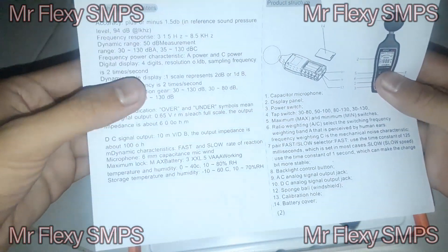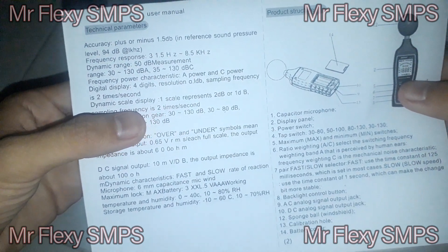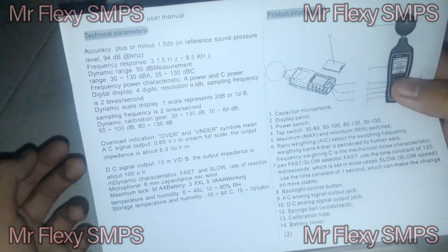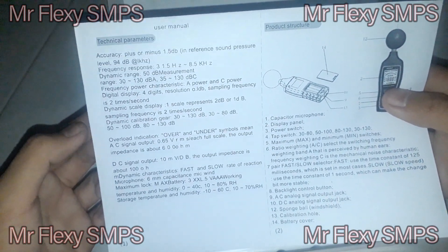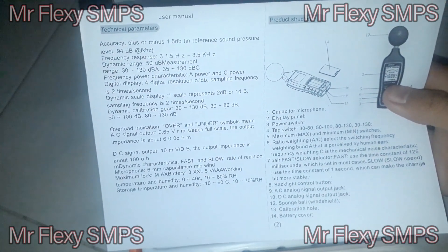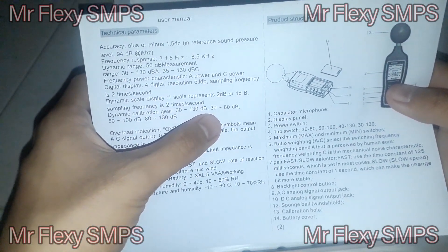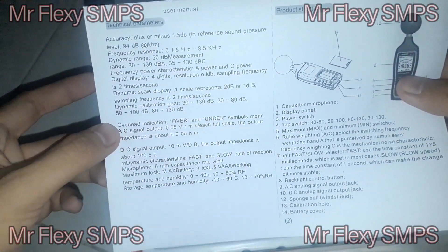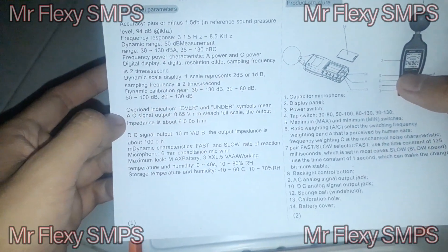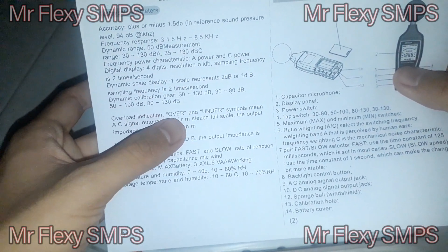Digital display is 4 digits, with a resolution of 0.1 dB. Sampling frequency is 2 times per second. The dynamic scale display has one scale representing 2 dB or 1 dB. Dynamic calibration gear ranges: 30 to 130 dB, 30 to 80 dB, 50 to 100 dB, and 80 to 130 dB. Overload indication uses over and under symbols. AC signal output is 0.65 volts RMS.